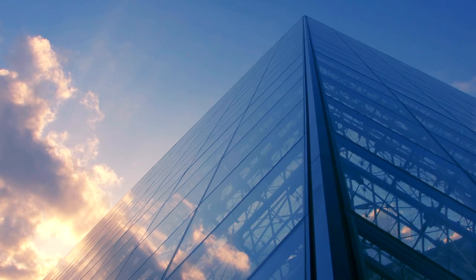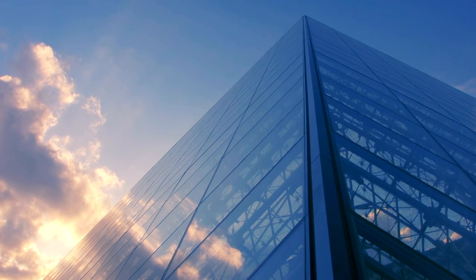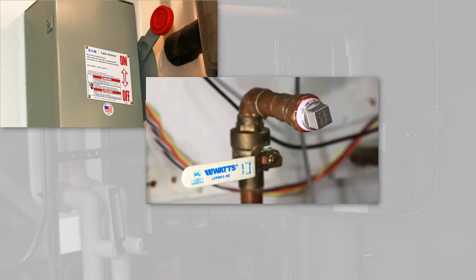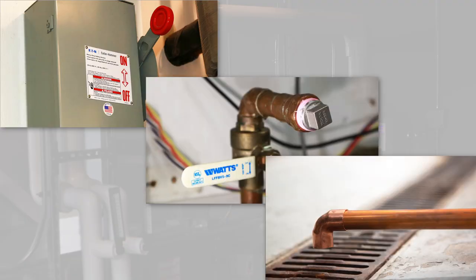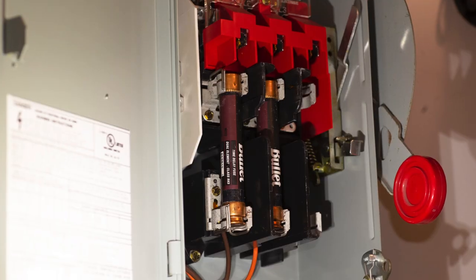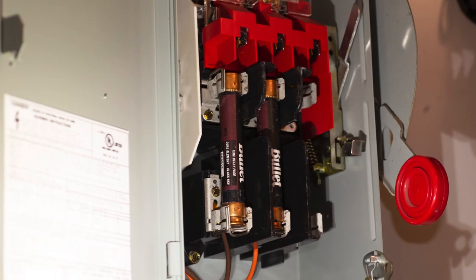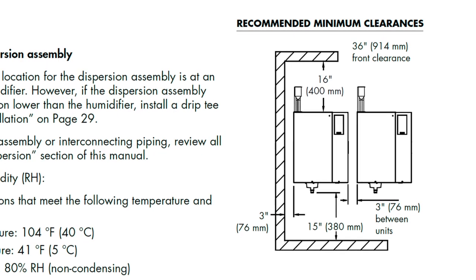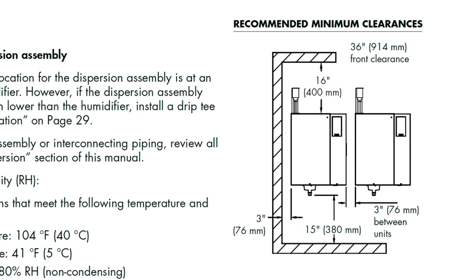Before you head out to the installation site here are some things you should verify. Installation location for the unit is clear and ready, power, water and drain have been run and are operational, code approved electrical disconnect, proper clearances per IOM.